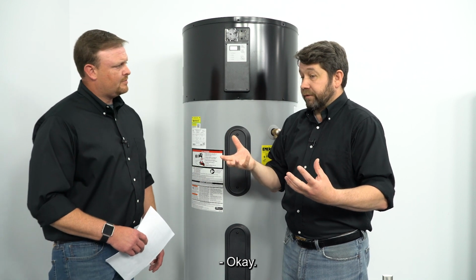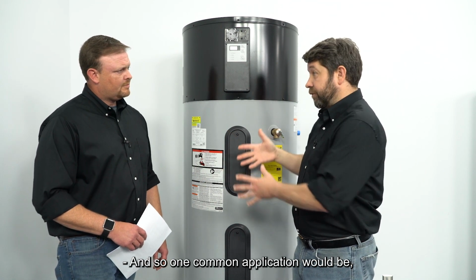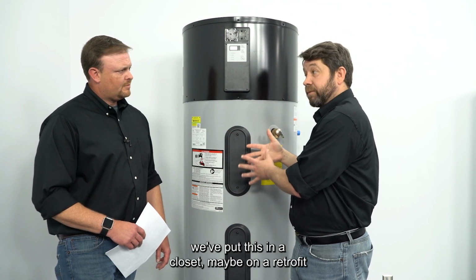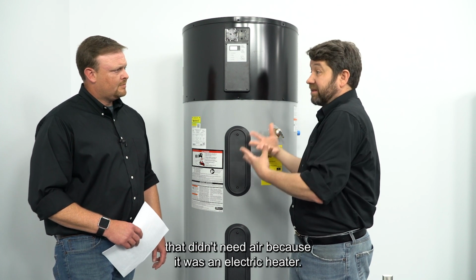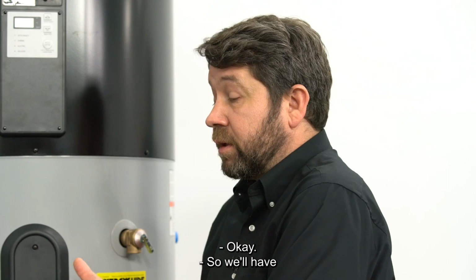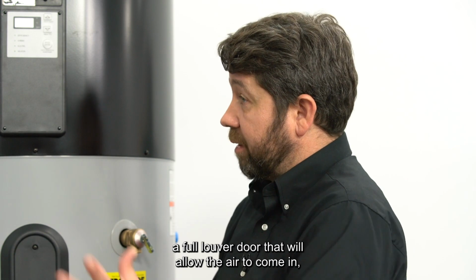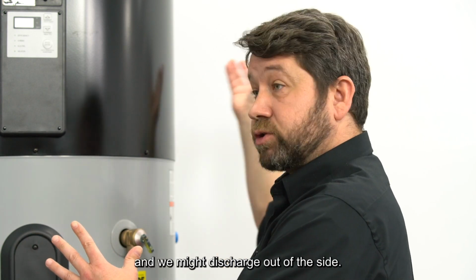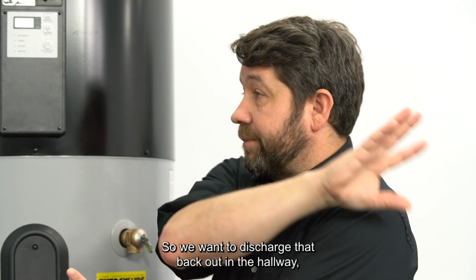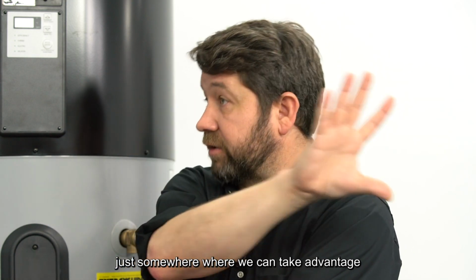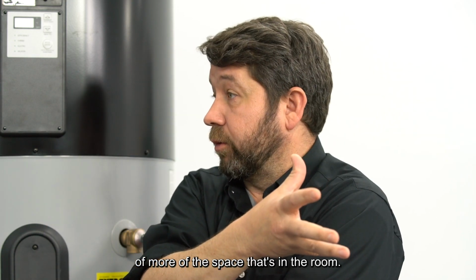Okay. And so one common application would be, we've put this in a closet, maybe on a retrofit where we had a water heater that was in the closet that didn't need air because it was an electric heater. Okay. So it will have a full louvered door that will allow the air to come in, and we might discharge out of the side. So we want to discharge that back out in the hallway, just somewhere where we can take advantage of more of the space that's in the room.